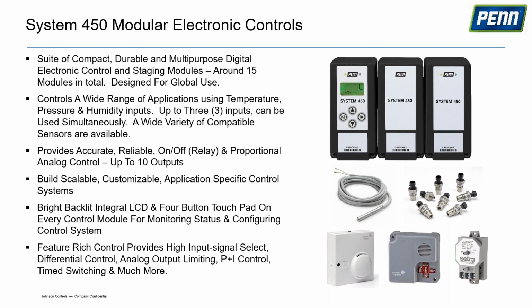You can also add what we call staging or expansion modules to add relay or analog output. So you can imagine the different types of applications that you can use this for. You can have a total of 10 outputs. There are 3 inputs that you can have to the controller, and those are temperature, humidity, and or pressure. And you can control on any 3 of those, or one of those if you prefer, at the same time. So again, if you start to think through the different applications that may require temperature and humidity, you can basically just choose and pay for the modules that you need for those particular applications.